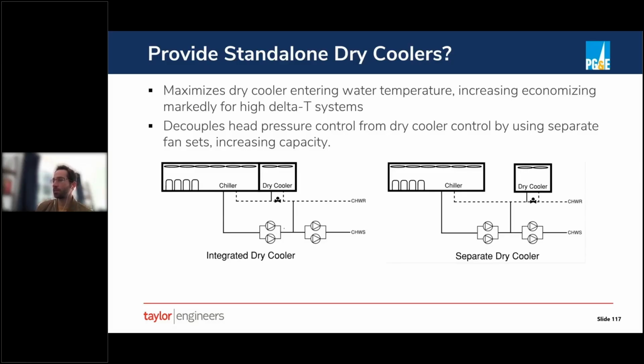So we can imagine a scenario where the primary flow is exceeding the secondary flow. So we have some flow going out chilled water supply. We have some of the flow that's coming this way through the decoupler, and then it's getting blended back with the chilled water return. And when that happens, the chilled water return temperature that the dry cooler sees is higher than the temperature coming back from the load.